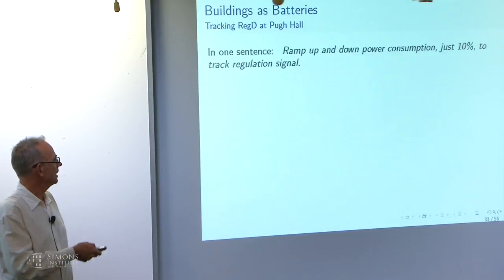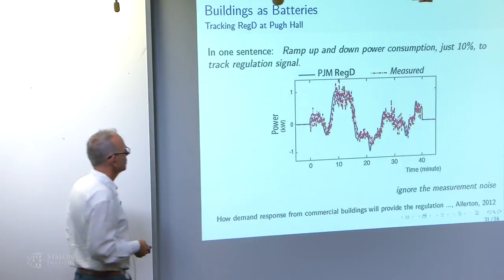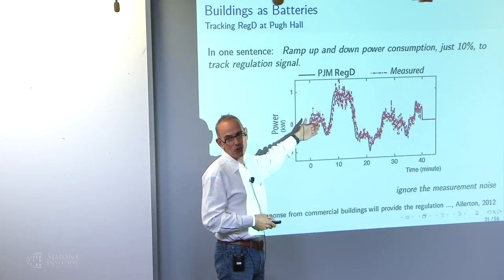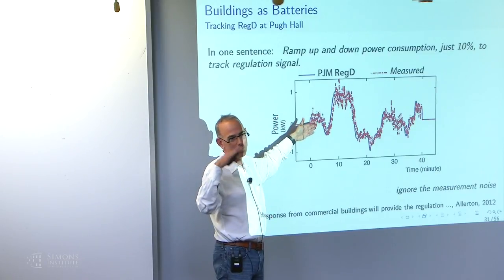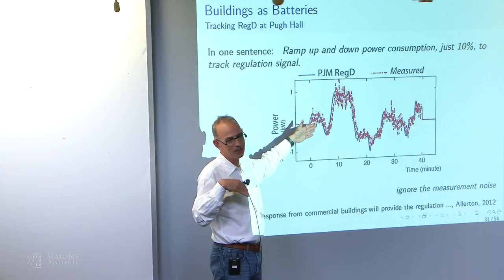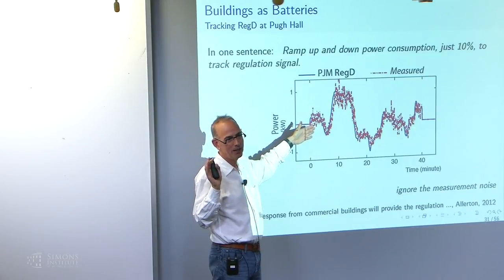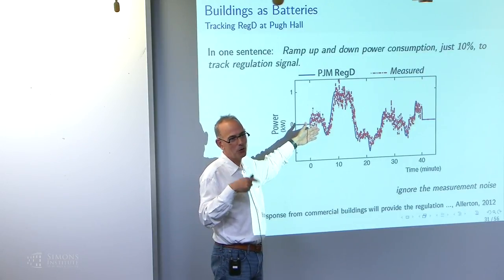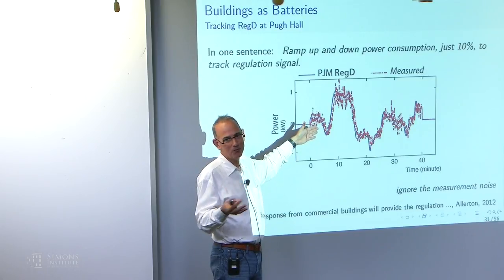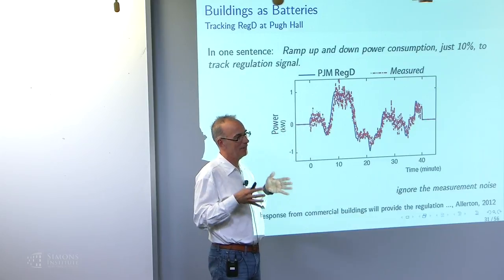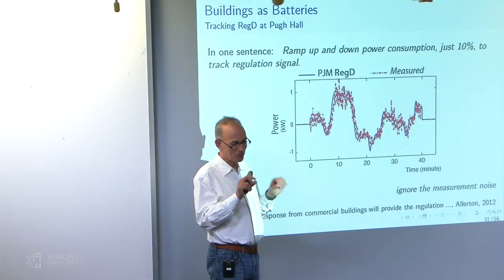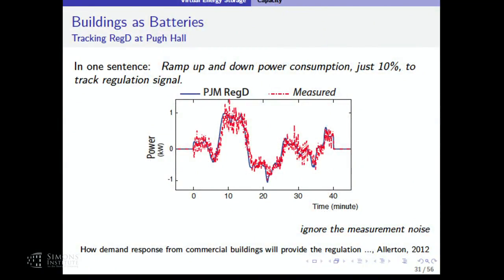Basically, you can track a Reg D signal perfectly by modulating fan speeds up and down. It doesn't affect anybody, nobody feels a thing. If you look at the fans before and after we got involved, they don't look any different. It's absolutely nothing. There's building automation equipment in the building, so you just have to write a few scripts of code. This noise is just measurement noise, since we didn't have the money for good sensors.